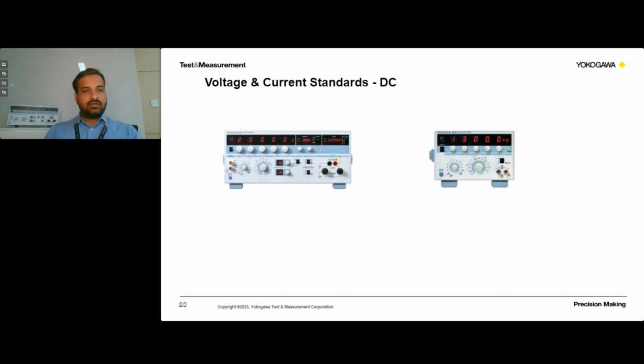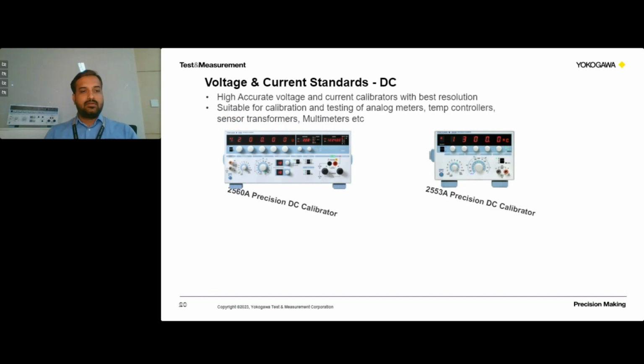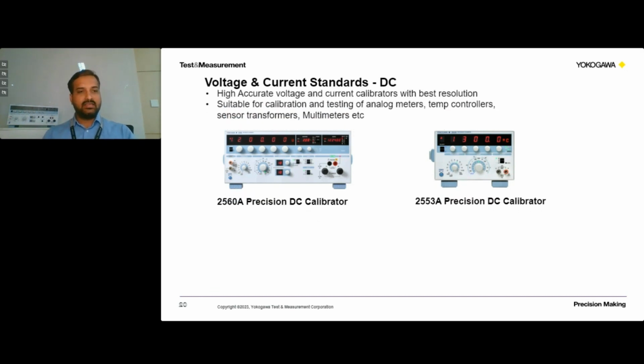Next, we have the voltage and current standards for DC applications. Here we have two models, 2560A and 2553A. These are also highly accurate voltage and current calibrators, the best available in the market with the best possible resolution. They are suitable for calibration and testing of analog meters, temperature controllers, sensors, sensor transformers, multimeters, those kinds of applications. We'll focus on each individual model, 2560A and 2553A, in detail.